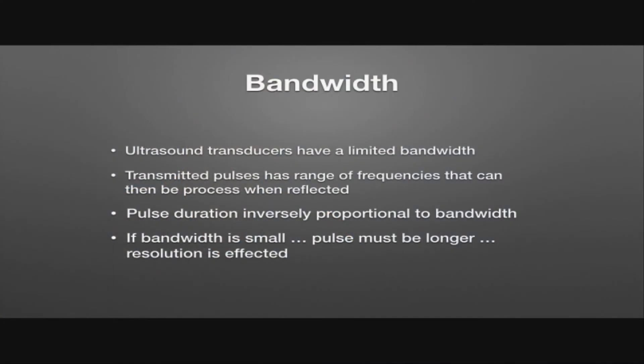Why is all of this important? It's important because ultrasound transducers have a limited bandwidth. If we're sending out transmitted pulses with a range of frequencies, we've got to be able to process that range of frequencies when it's reflected. Since pulse duration is inversely proportional to bandwidth, if we have a limited bandwidth, that means we're going to have a limited pulse duration. If the bandwidth is small, the pulse has got to be longer, and that means resolution is then going to be affected.